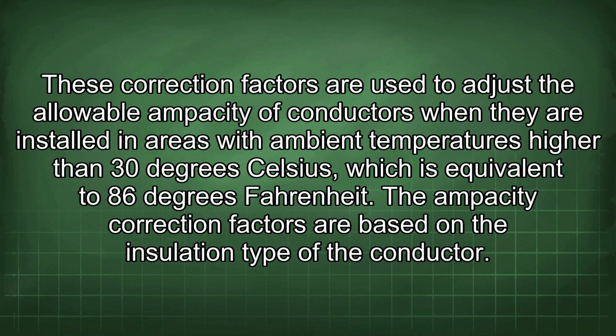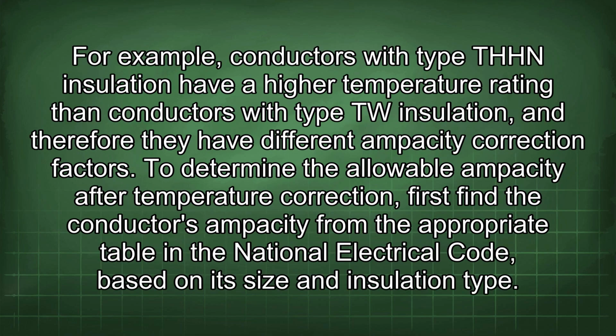The ampacity correction factors are based on the insulation type of the conductor. For example, conductors with type THHN insulation have a higher temperature rating than conductors with type TW insulation, and therefore they have different ampacity correction factors.